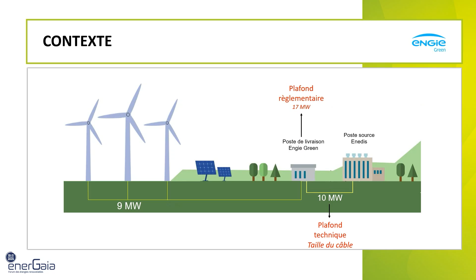When we see this, we want to add PV panels, and the mistake we mustn't make is to say, well, there's 1 mega left in the cable, so we can install 1 mega of PV and send it through the cable. But no, hybridization would be to install 8 megawatts of PV, because 9 and 8 make 17, so we fit within the regulatory ceiling. The 10 mega cable is still there.